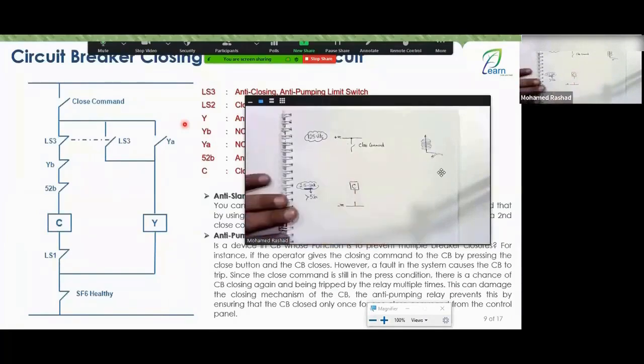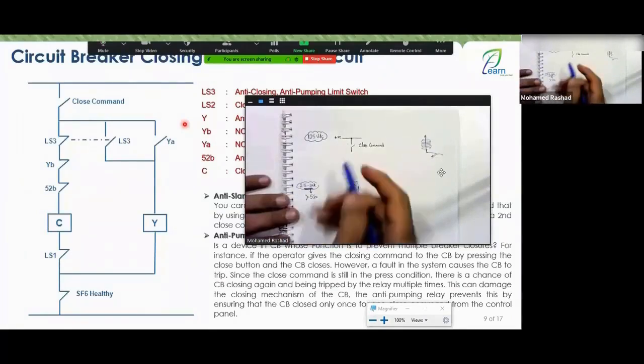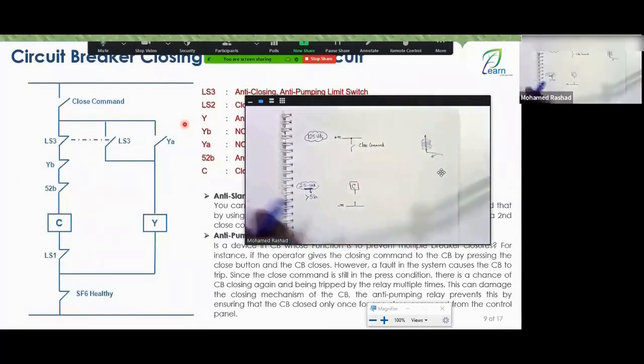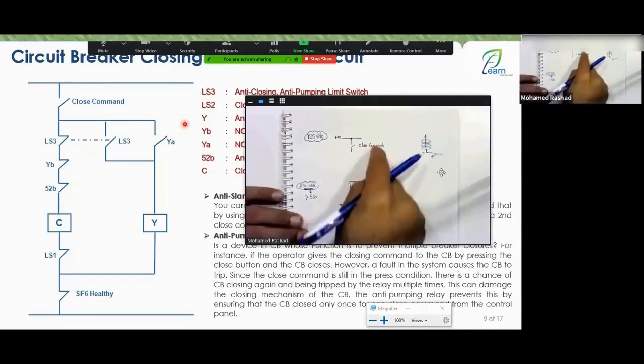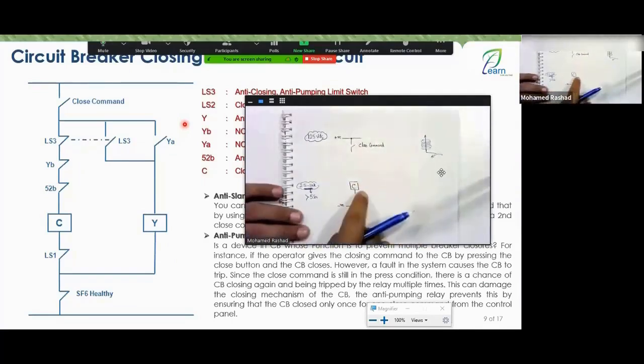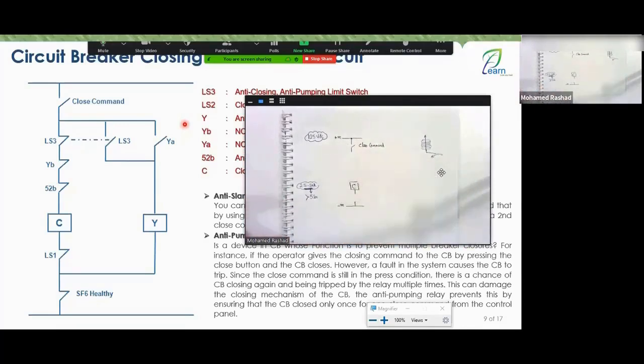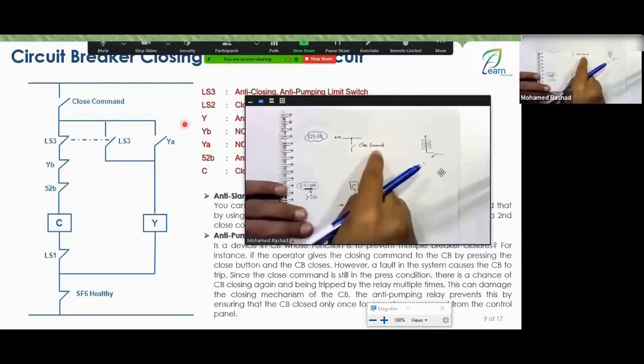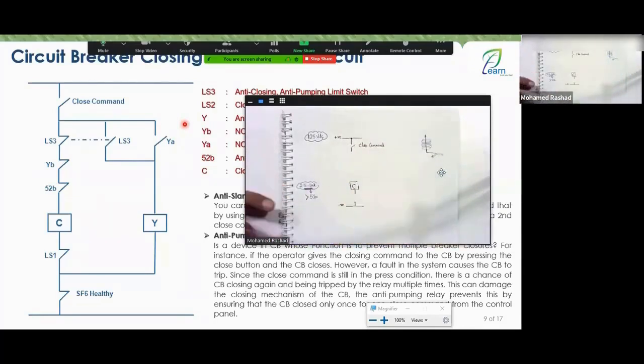Okay, let's go step by step. You will close the breaker, and close the breaker, and close the breaker again. The second close command from your control will receive a DC here. The breaker is already closed. Someone had closed it before and you came to this. This is a close command again. Do you have a problem? No, of course not, because the breaker was already closed. But do you have a problem if it doesn't give a close command again?